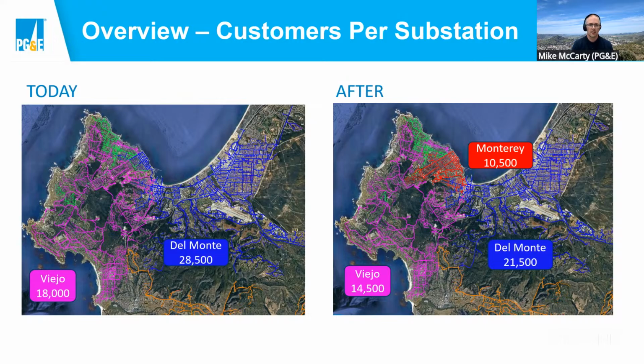As a high-level example, if we had a loss of Viejo—which wouldn't necessarily happen for both transformer banks there, but just for this example—that would put 18,000 customers out of power today. In the future, that decreases to 14,500. So the outage exposure to those customers decreases, and since the lines themselves are shorter, the exposure to outages on the lines also decreases.